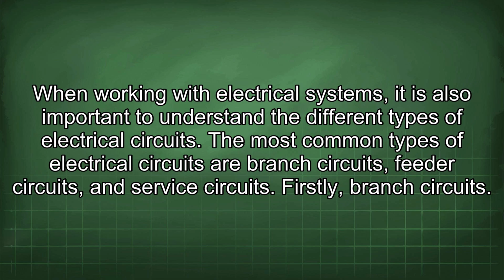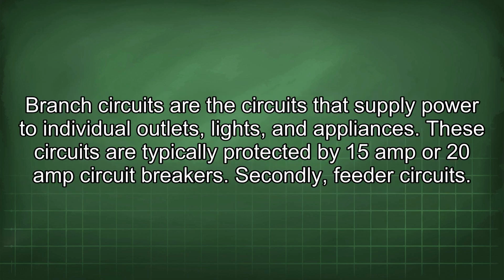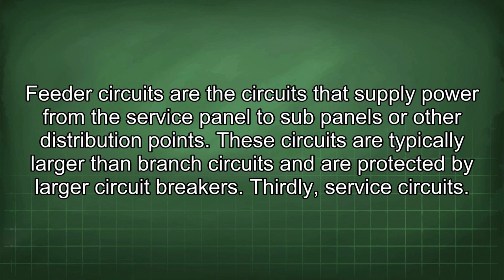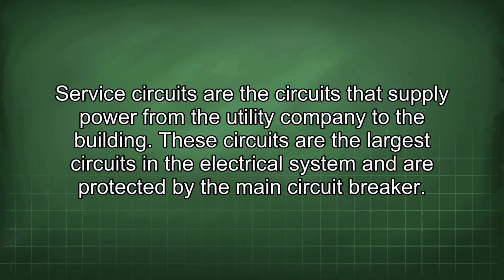Firstly, branch circuits. Branch circuits are the circuits that supply power to individual outlets, lights, and appliances. These circuits are typically protected by 15 amp or 20 amp circuit breakers. Secondly, feeder circuits. Feeder circuits are the circuits that supply power from the service panel to sub-panels or other distribution points. These circuits are typically larger than branch circuits and are protected by larger circuit breakers. Thirdly, service circuits. Service circuits are the circuits that supply power from the utility company to the building. These circuits are the largest circuits in the electrical system and are protected by the main circuit breaker.